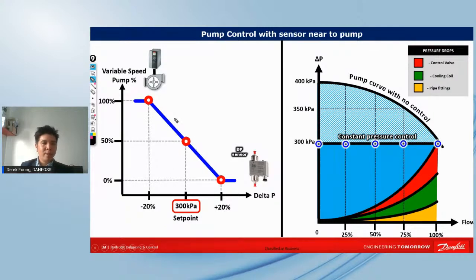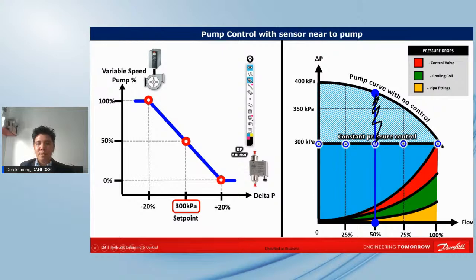So it is a proportional control right here. And of course, we can see that this shaded area is the potential energy saved. So if the flow rate is reduced down to 50%, then the area of energy saving is right here. You can see this is around 30% of the energy saved, without accounting for a lot of efficiencies at the moment, right? So this is like taking the slightly surface-level view at the moment.